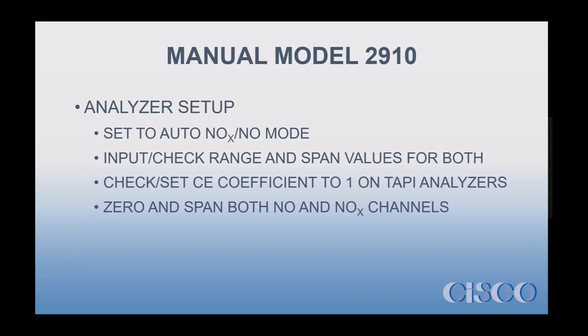But anyway, to verify that and include it in the report, so the report does meet 40 CFR 86 requirements, we were calculating off the value of the analyzer. Well, the cylinder we have on our training system right there, there's 0.02 ppm NO2 in the cylinder. And we were coming up with negative efficiencies just due to the noise of the analyzer and the cal error in the analyzers, okay? So we had to back up our software and say, okay, we're going to calculate the efficiency off the values on the cylinder, not off reading off the analyzer, because the analyzers are not that accurate that you can figure out 0.02 ppm. Okay.